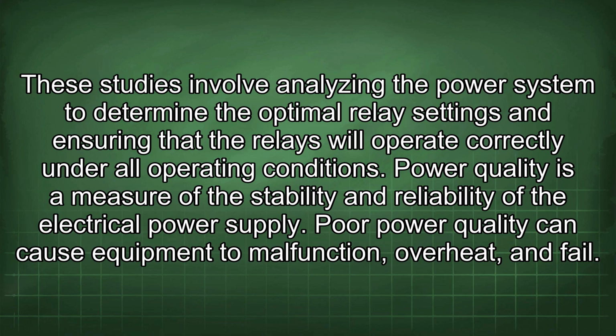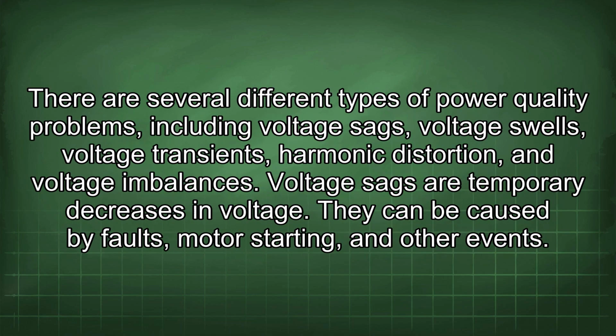Power quality is a measure of the stability and reliability of the electrical power supply. Poor power quality can cause equipment to malfunction, overheat, and fail. There are several different types of power quality problems, including voltage sags, voltage swells, voltage transients, harmonic distortion, and voltage imbalances. Voltage sags are temporary decreases in voltage.